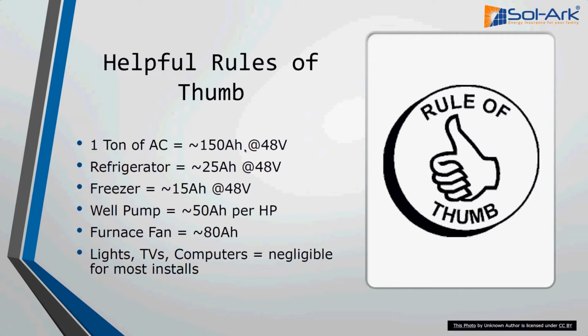As you can see, air conditioning is huge. Refrigerators, not that bad. Freezers, really not that bad. Well pumps don't need a whole lot for continuous demand, but something to note is that they're an inductive load, so they have a pretty high peak power demand when they first turn on. For example, one Sol-Ark 12K or 8K is capable of dealing with about 3 horsepower of startup, so bear that in mind whenever you're dealing with inductive loads like pumps, air conditioning, and so on.